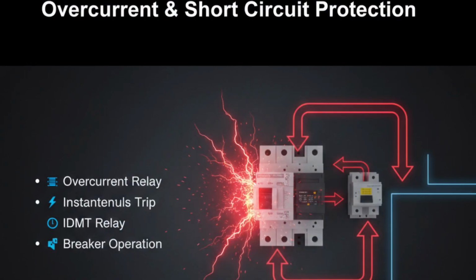Overcurrent or short circuit protection. Here we focus on overcurrent and short circuit protection, which is the most basic yet essential protection in any generator system. When current exceeds the rated value, overheating occurs in stator windings. Overcurrent relays continuously monitor current levels. If current crosses preset limits, the relay sends a signal to trip the breaker. Instantaneous relays act immediately during severe short circuits. IDMT, inverse definite minimum time, relays allow temporary overload but trip if the fault persists.